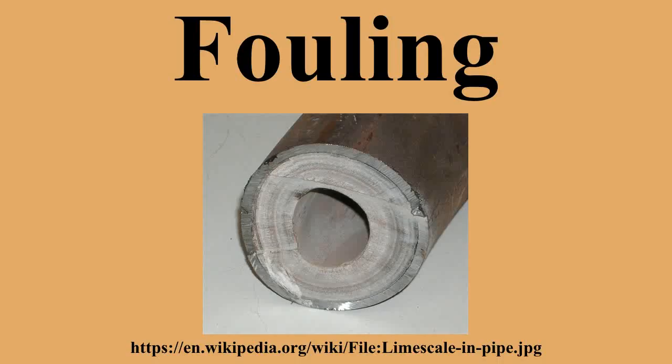On the component design level, fouling can often be minimized by maintaining a relatively high and uniform fluid velocity throughout the component. Stagnant regions need to be eliminated. Components are normally over-designed to accommodate the fouling anticipated between cleanings. However, a significant over-design can be a design error because it may lead to increased fouling due to reduced velocities. Periodic online pressure pulses or backflow can be effective if the capability is carefully incorporated at the design time.